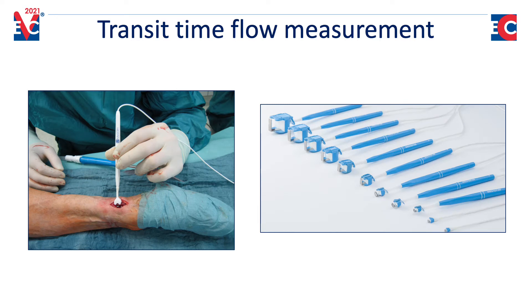All you need is a flow probe with two single transducer elements, consisting of a transmitting and a receiving transducer. On the other side we have a reflector sending the waves back to the transducers. There is a wide range of different sizes of flow probes available.